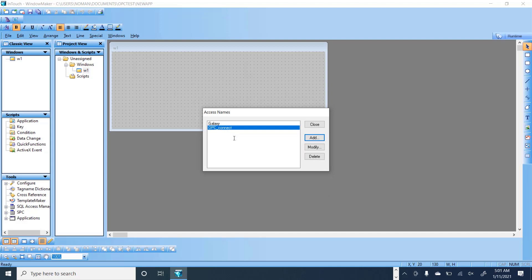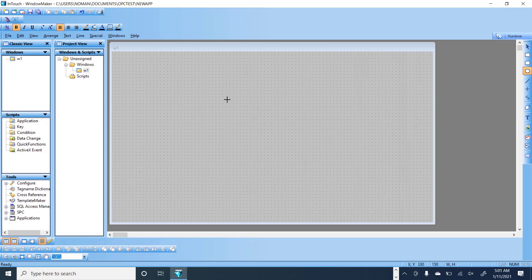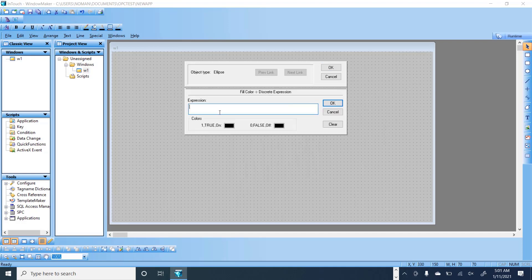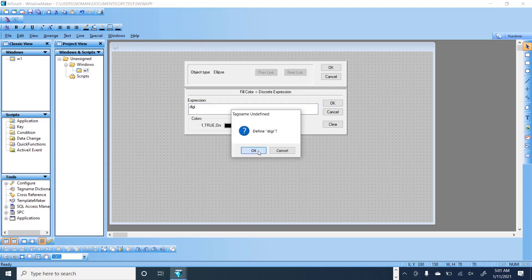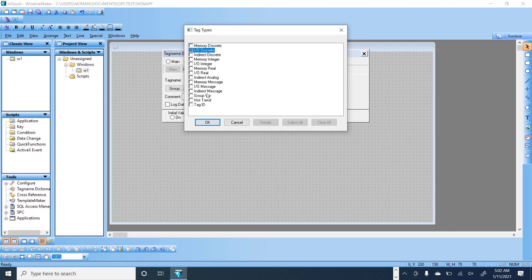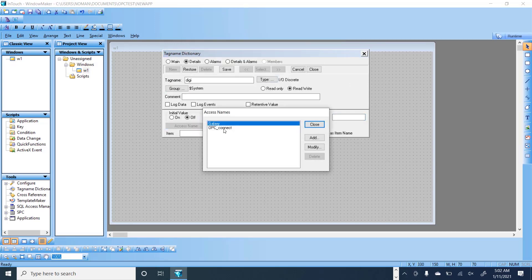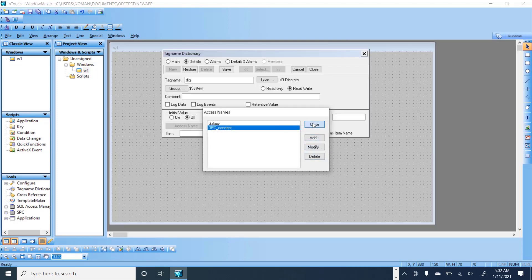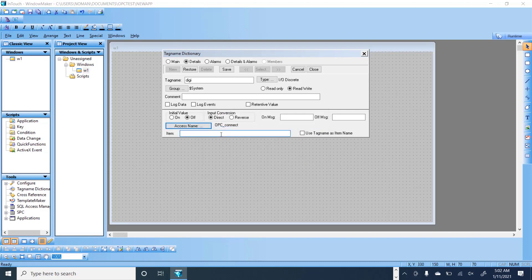Now define a tag. Double-click to open the tagname dictionary, go to Discrete, and name it 'dig' for digital. Select OK. Set the tag type to IO Discrete, assign the access name 'OPC connect', click OK, then close and set the address to M0.0.